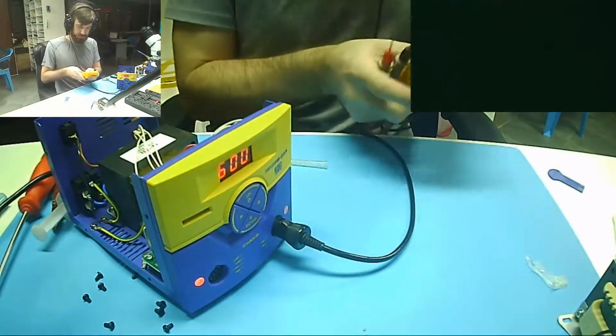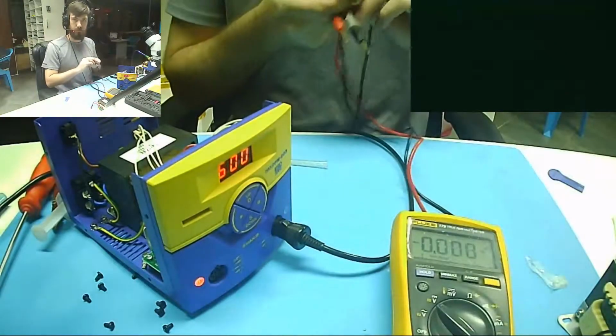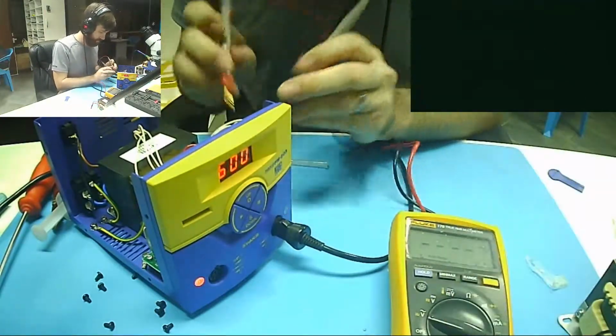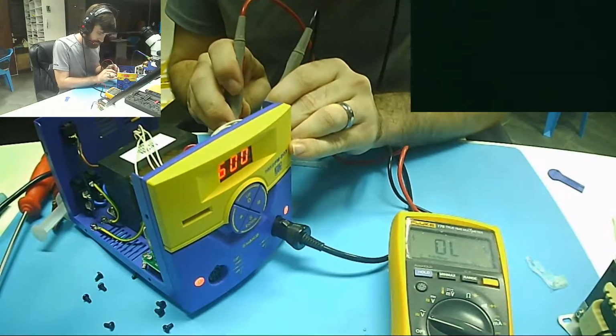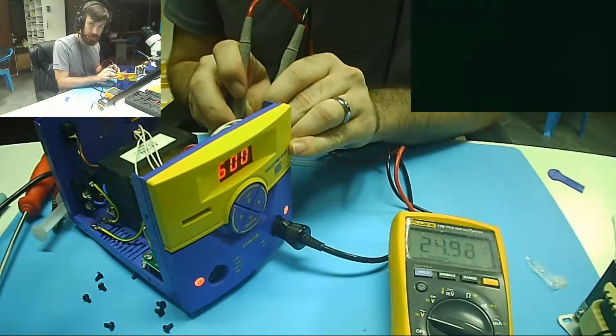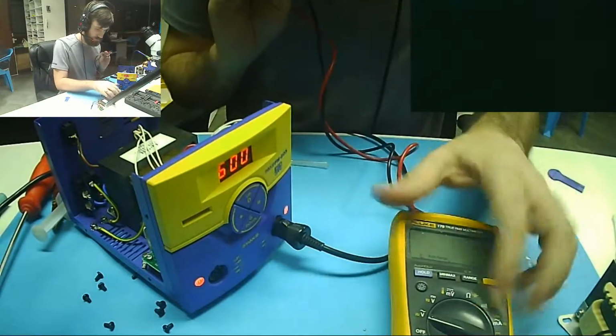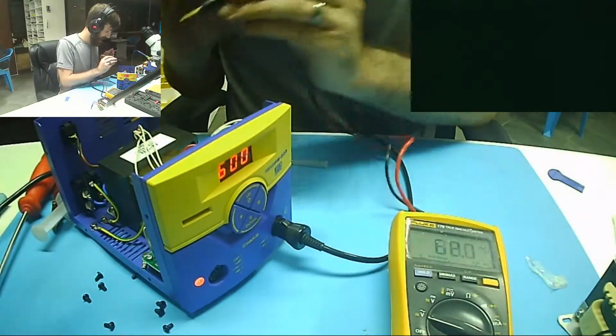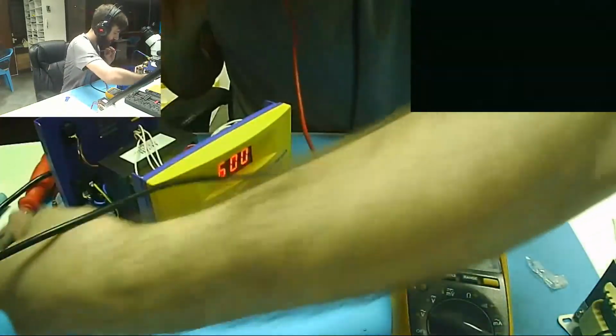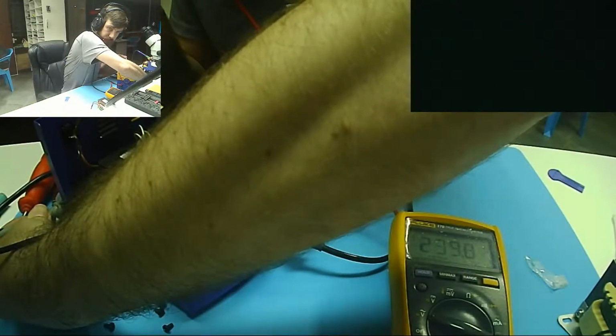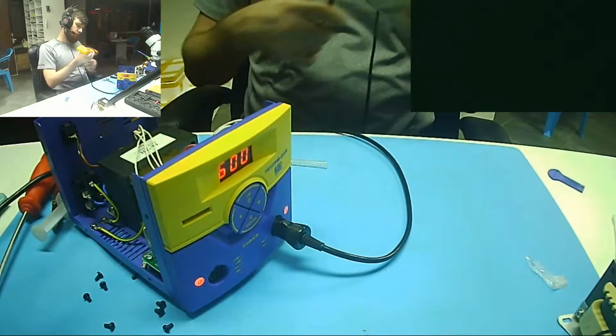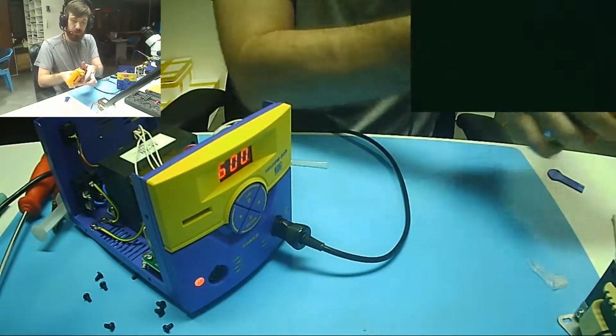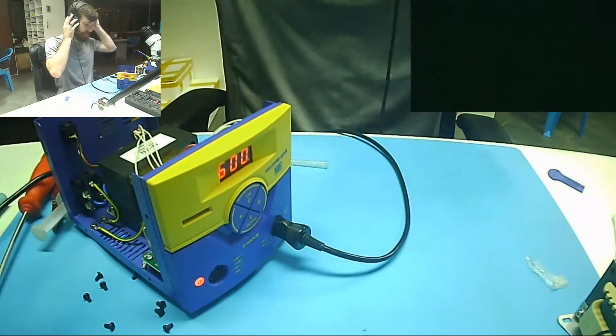this transformer is outputting an AC, because that's what we're using here. Flip, flip. 24.93 volts, so 25 volts. And that is with our, at the moment, voltage of, can you see that? You can see that good. 235-ish volts. Our voltage here varies a lot, which sucks, which is why I went with a 240 volt instead of the 230 or 220 volt transformer, just because I know that the voltage here is not necessarily what it needs to be.